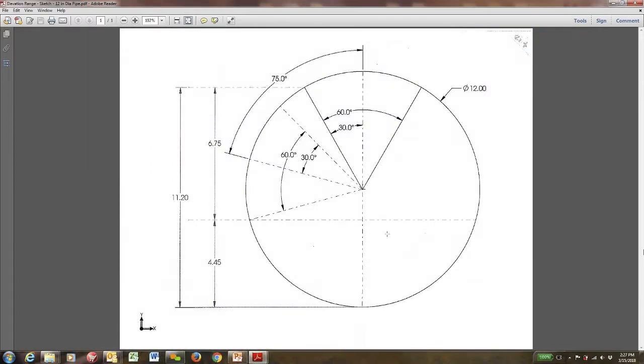When I'm talking to engineers about how big a diameter pipe they need, this is a 12-inch diameter cross-section view of a rotating scum pipe, 75-degree rotation, 60-degree slots, and we talk about how much room is available for skimming based on the change in water elevation that I was talking about earlier. So we've got one of these for all the different diameter pipes, and I can get the engineer on here, and we use Join Me just like we are right now, so I can talk it through with your engineer and help develop those specs to our best advantage to get the job.